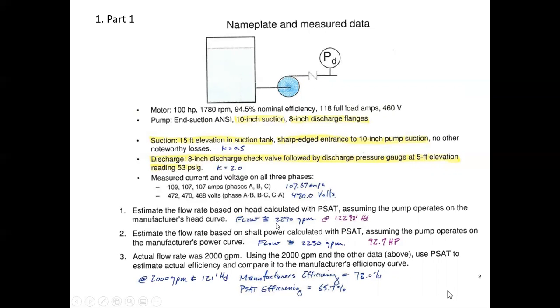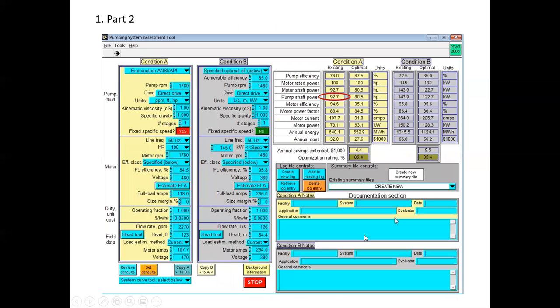Okay, so there's 1. Then 2 says estimate the flow based on the shaft power calculated in PSAT, assuming the pump operates on the manufacturer's curve. Okay, so this condition A is what I'm looking at over here. This is garbage in condition B, so don't look at that. But anyway, I think I've put in the pump and fluid information correctly.